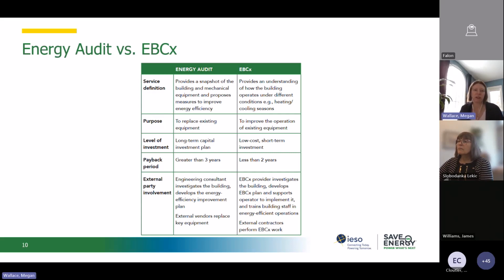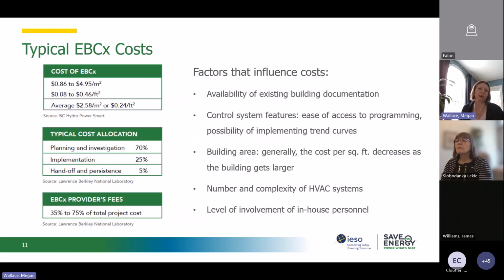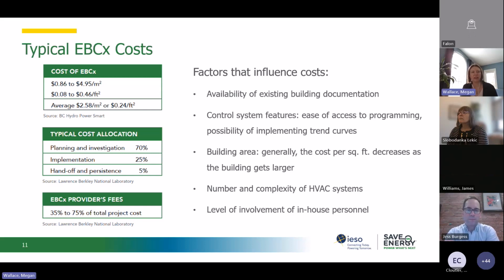For EBCx, the EBCx provider investigates the building, develops an EBCx plan, works with the owner to implement it, and trains the building staff to continue the process. Then external contractors are used to perform the EBCx work, such as an air balancing contractor or BAS contractor. So some of the costs associated with EBCx: you look at an average cost of about 24 cents a square foot. And typically that cost is allocated 70% for the planning and investigation phase, so a lot of work goes into the beginning stages of this, 25% for the implementation, and then 5% for that handoff and persistence phase.